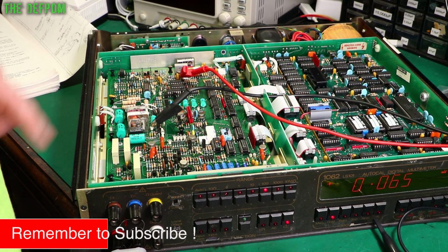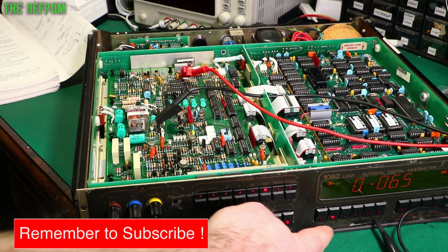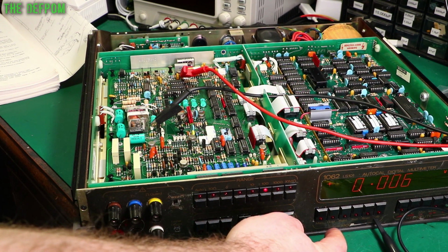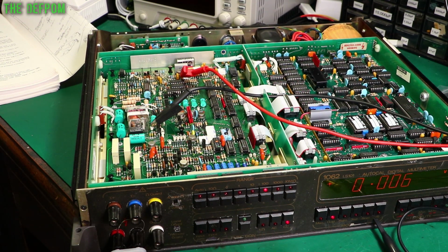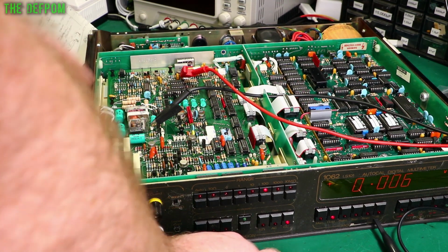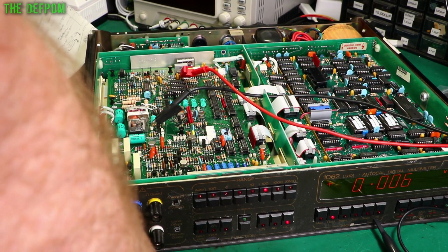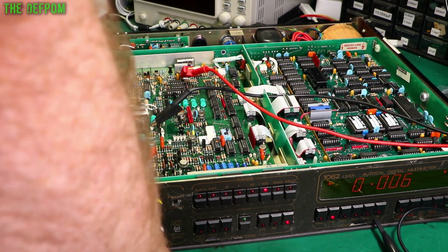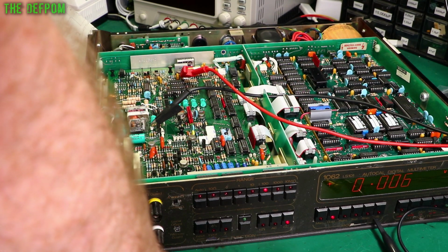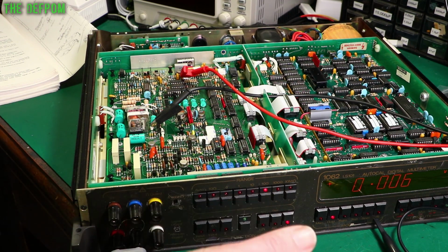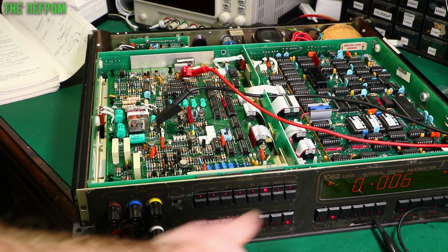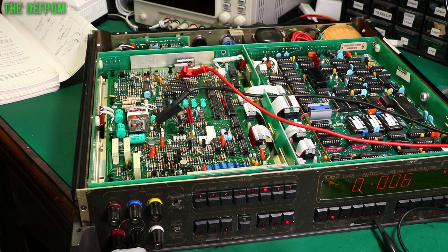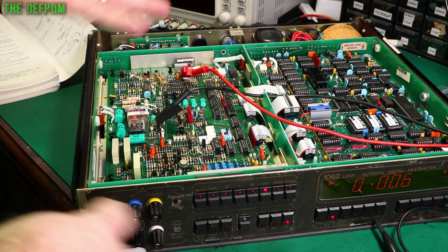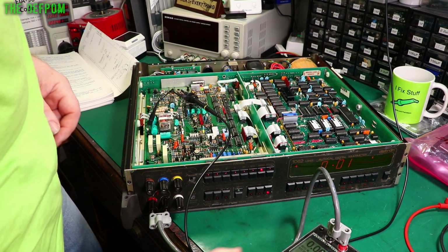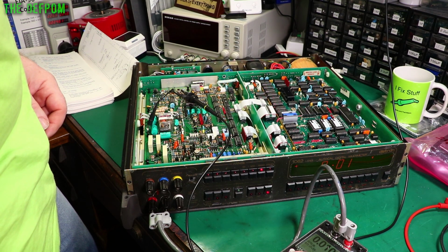So TP9 is over here. The next check is to be on hold range. Just going to unhold it and then rehold it again since I've changed ranges. Now I need to make sure that the voltage at TP9 here is less than 1 millivolt. Well, 0 volt plus or minus 1 millivolt. And this is another factory selected value resistor. This is more verification that it's actually still okay. I'm getting 0.39, so 390 microvolts, so that's within spec, so I don't have to worry about that part, that's fine.